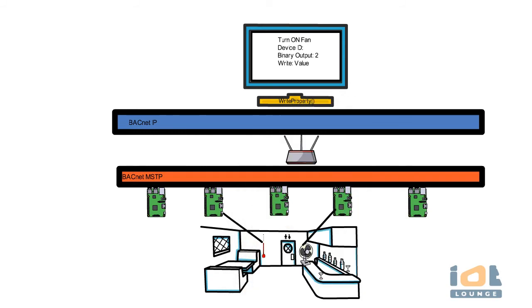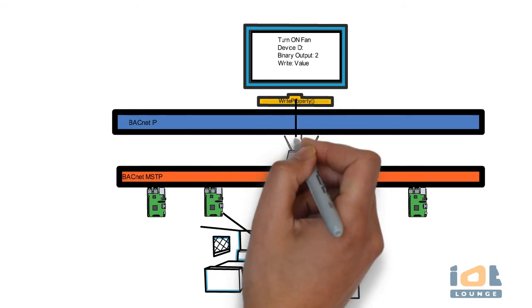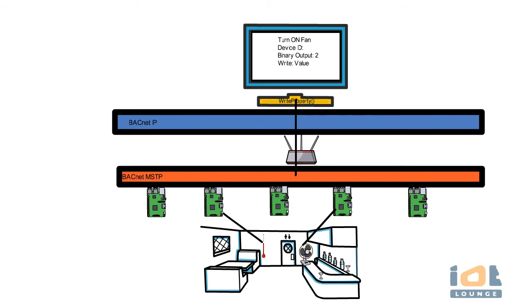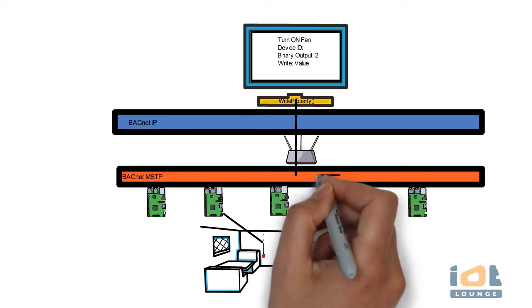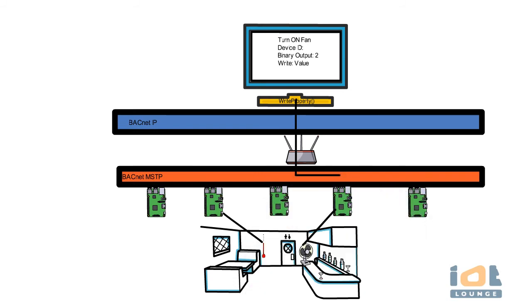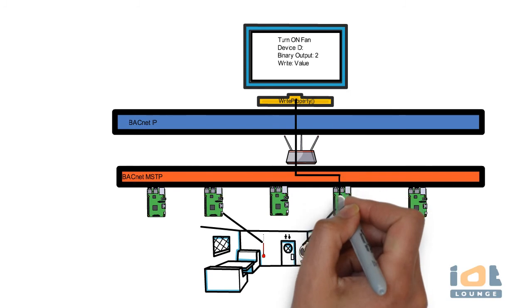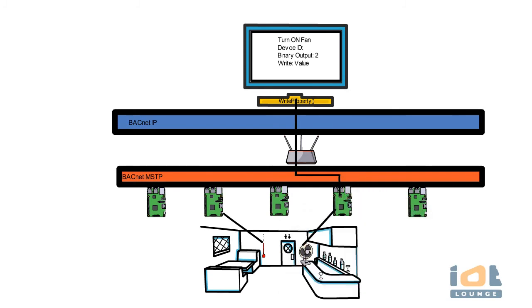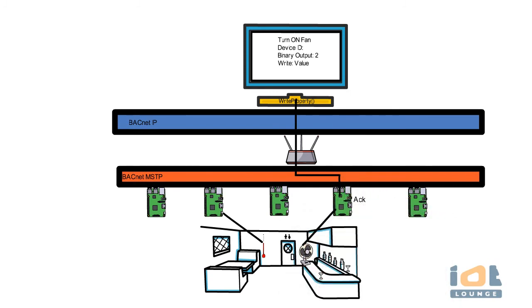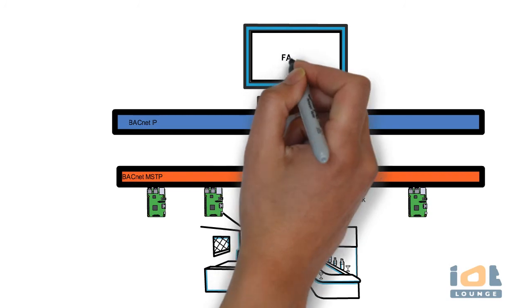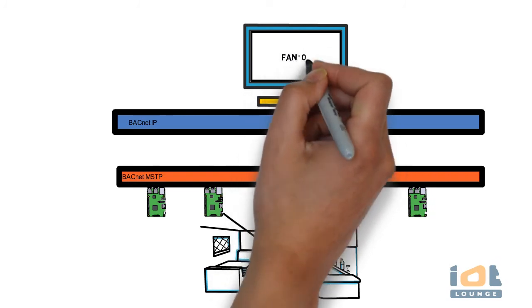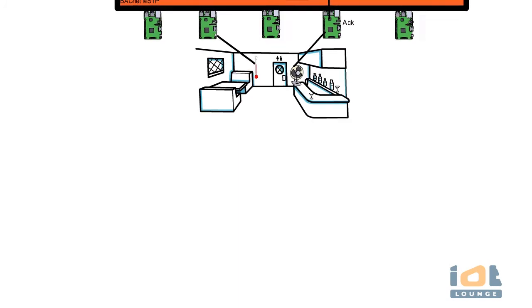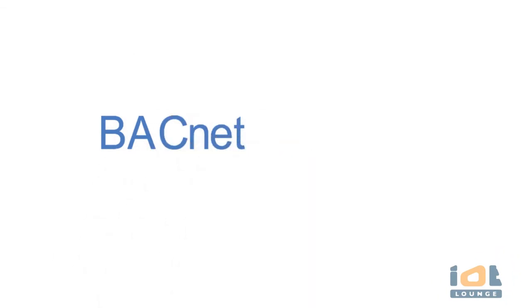To turn a fan on an air handling unit, the user selects the device and the binary output which the fan is connected from the enterprise BACnet software. The protocol sends a write property service targeting the selected device. The packet traverses between the IP and MSTP layer via the router to the destination device. The device triggers output to on state and responds back with an acknowledgement to the software for confirmation.